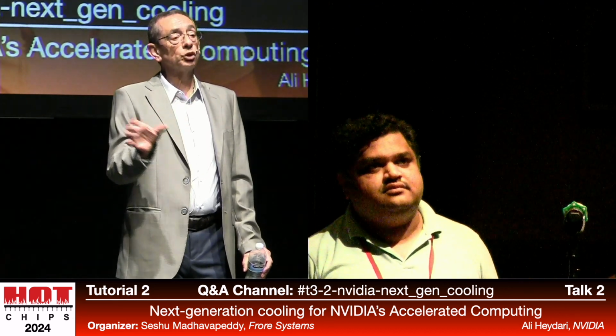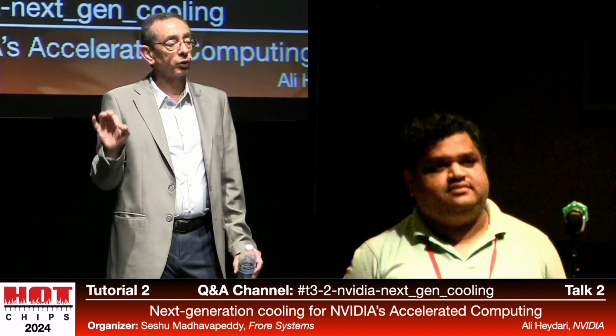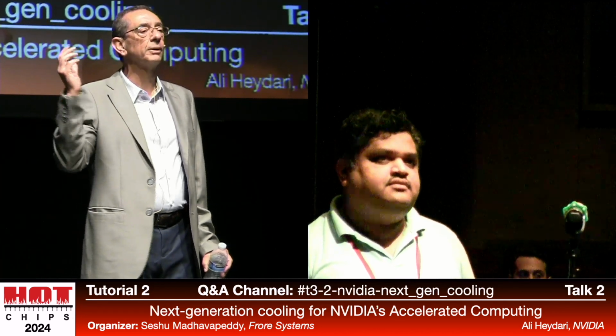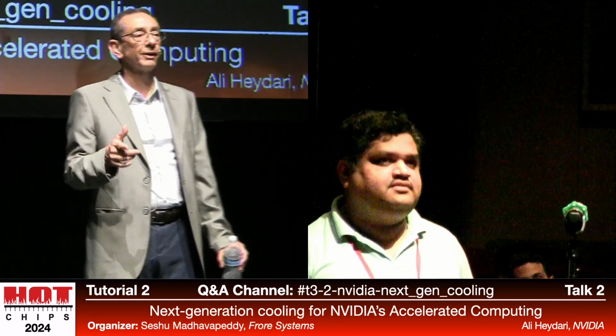In our research, PG25, 25% propylene glycol, if it is run continuously, has the lowest potential in terms of biogrowth and settling. So when you have PG25 continuously circulating within the loop, the maintenance requirement becomes minimized, and that follows what I consider liquid cooling. Always thought about it as high power delivered to the racks. I don't want anybody to see a single drop of liquid. You don't want to see an electron jump out of your cables. You don't want to see a single drop of liquid jump out of your tubes. You don't want to have to go and maintain your liquid line because you don't maintain your air lines.